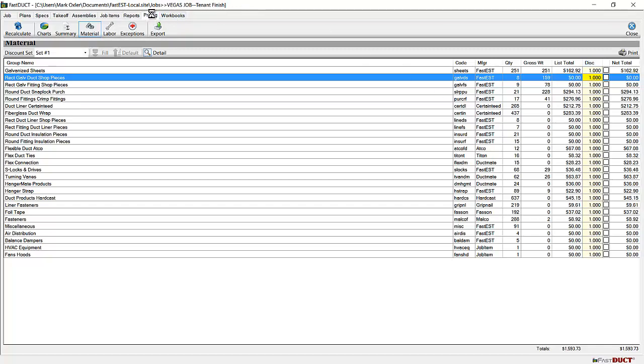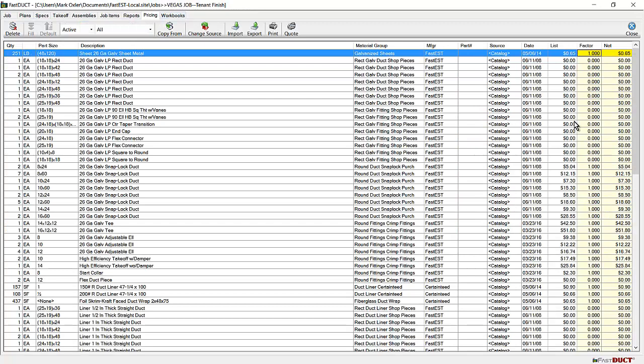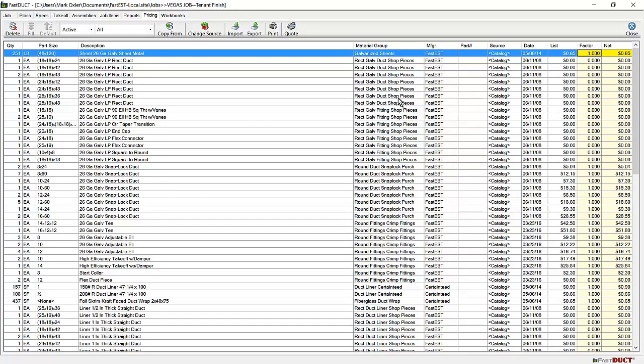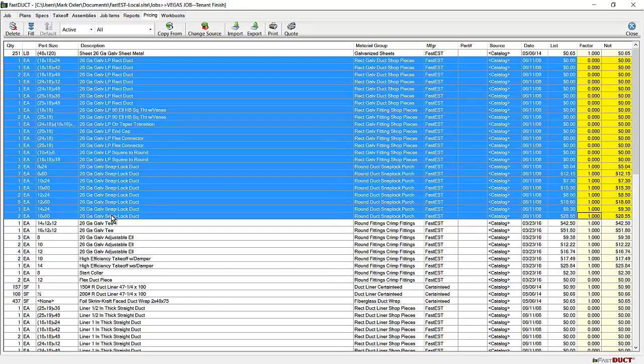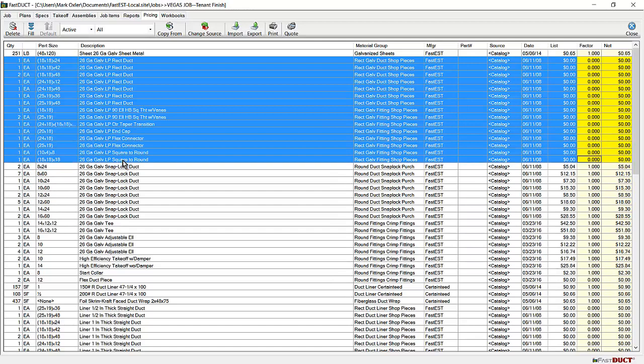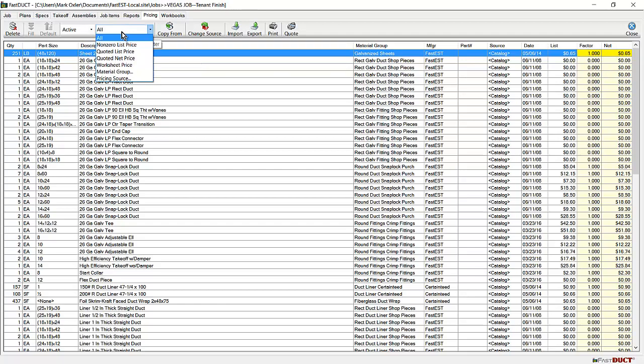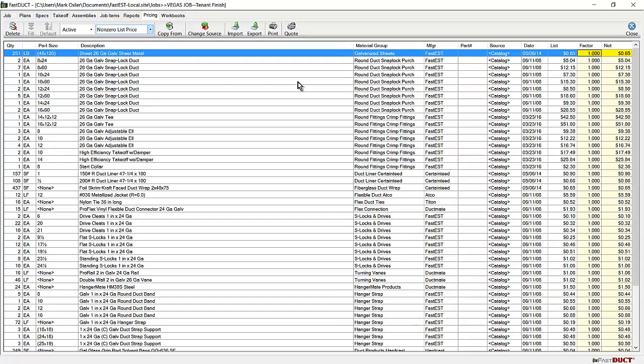You can also alter pricing at the pricing page. Each item on the project, whether it's taken off or generated from the specs, is shown on the pricing page, and you can adjust the net pricing. In the duct program, fabricated and purchased duct pieces will show up as zero on the pricing page because the cost is transferred into the raw material from which the item is built. Here you see we have 251 pounds of 26 gauge sheet metal. There's a special report in the FastDuct program for non-zero list price to hide these items which will normally be zero.